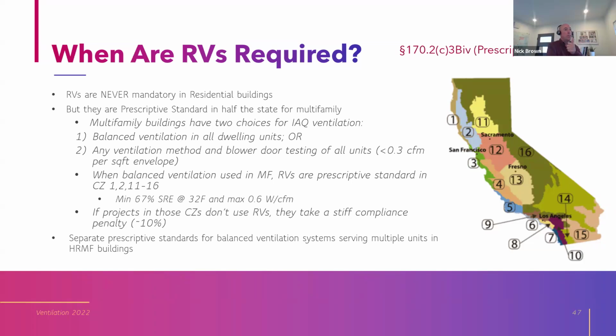Right? So if you use balanced ventilation in these climate zones, the standard design is going to have heat recovery. If you don't have heat recovery, you're going to take that 10% average compliance penalty, depending on what climate zone you're in, right? So if you guys are working on multifamily projects, you're finding balanced ventilation performs way worse than exhaust, that's why. And there's a minimum 67% recovery effectiveness and maximum 0.6 watts per CFM for balanced ventilation. Under the prescriptive method, of course, if you use the performance method, you plug in whatever you're installing.